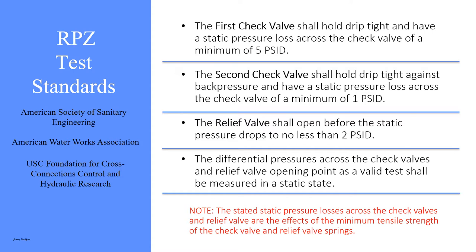The relief valve shall open before the static pressure drops to no less than 2 PSID. The differential pressure across the check valves and relief valve opening point, as a valid test, shall be measured in a static state. Note: the stated static pressure losses across the check valves and relief valve are the effects of the minimum tensile strength of the check valve and relief valve springs.